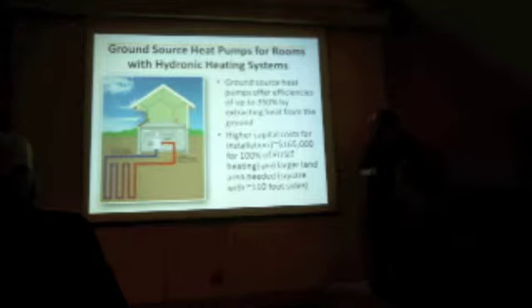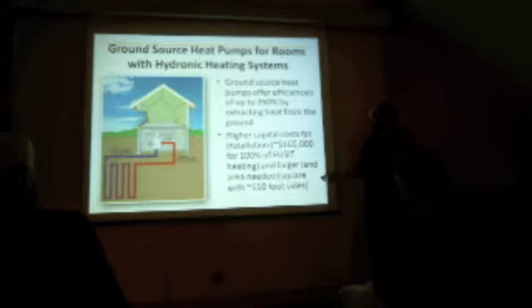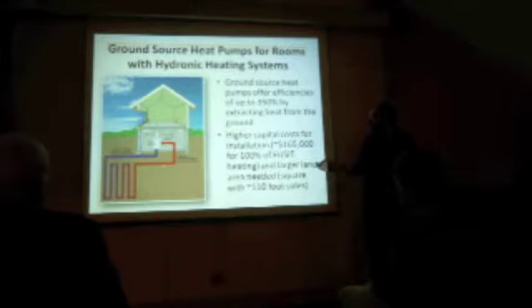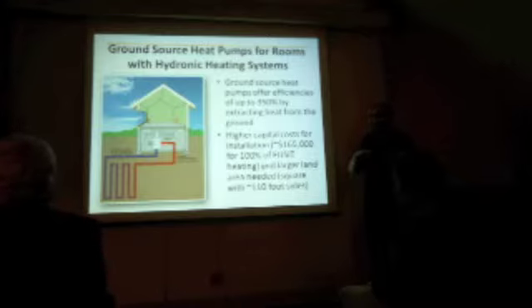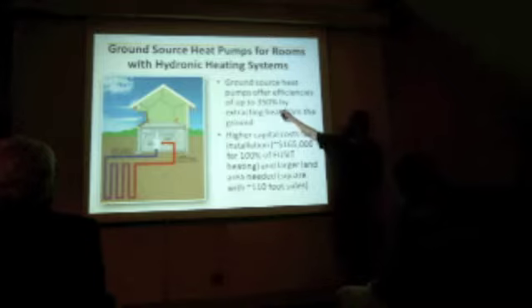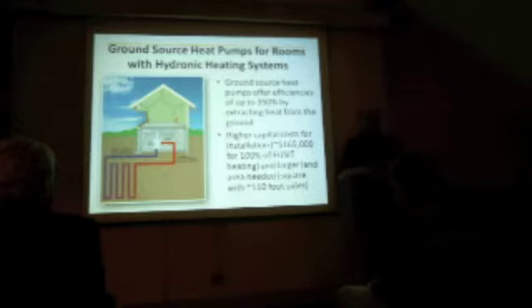So the other technology, the other heat pump that you may have heard about, is called a ground source heat pump. It does the same basic thing: you're extracting heat from the ground. You send the cold water out and the ground heats it up, and you're getting all that heat energy from the ground for free, just as you were getting the energy that it could extract from the air without having to supply it. The difference is that the ground is basically always at about 50 degrees once you go down a few feet, and therefore instead of trying to extract energy from 20-degree air, you're extracting heat from 50-degree ground. So these are more efficient. Instead of 200% efficient, they're 350% efficient.